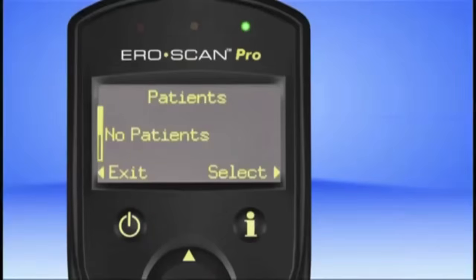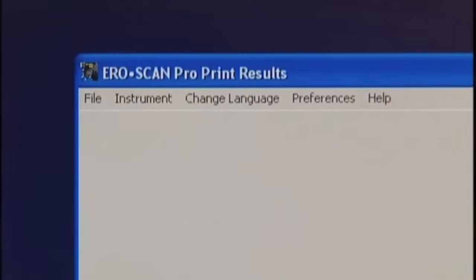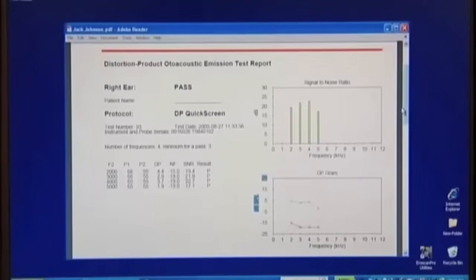The Ero Scan Pro can quickly print all the test results stored in the unit. In order to be able to print, you must have completed the system setup, which is described in detail in the next section. In the default mode, which is the single patient mode, or in the enhanced mode called numbered patients, all tests will be printed when the Ero Scan Pro is placed in its cradle. For this to happen, the Print Results application must be open on your PC. This application allows the option to print to either a PDF file or directly to the default PC printer. The details of this software setup are explained in the System Setup section.